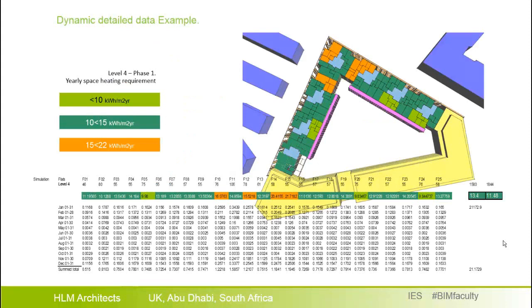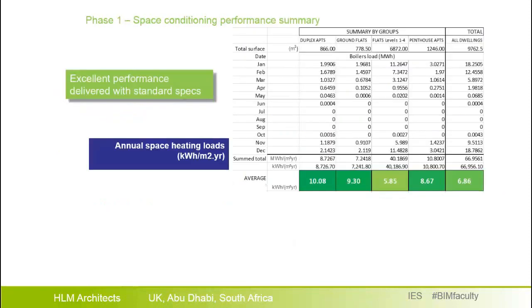This chart and mapped graphic presents an example of the information we use during design. It shows the space heating demand performance per square meter per year. This is from an ongoing process and not the final design. The apartments in orange were those exceeding 15 kWh per square meter per year, and this has been optimized to a more homogeneous performance in the current design, which is subject to further improvement.